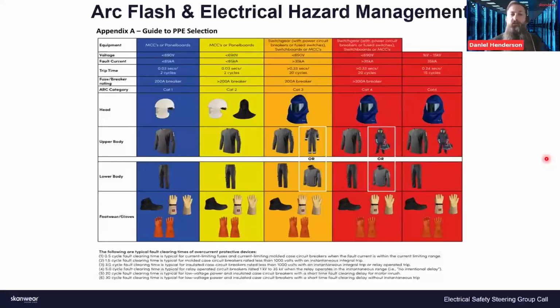Something I supported was in the US, 20 panels being isolated on a 28 panel board. It was in summer outside, red hot, on a 13.8 kV switchboard, in a 40-cal suit, isolating 20 breakers, then going to the rear of the panel to remove 20 rear covers with a tool, then discharging the capacitance in the MV cables, proving dead, then applying your portable ground 20 times in that type. So it's great to know having a 40-cal suit for that, or the company safety person also wearing a 40-cal suit with a rescue pole, things like that.